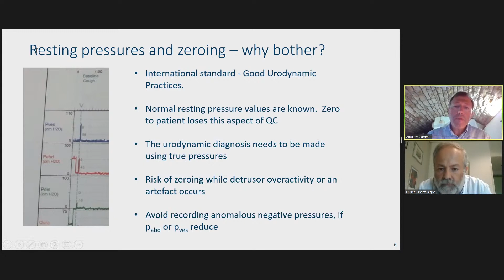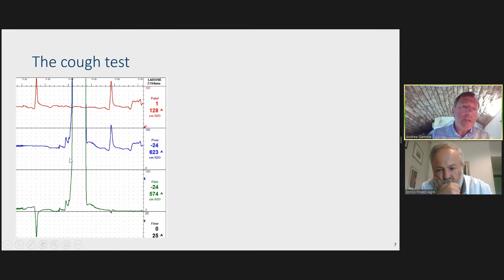So if I move us on to the next item of quality, which is the cough test, and many of us are familiar with this, I'm sure. Here's a good example where the patient coughs on this left-hand side, and the abdominal pressure goes up beautifully, but there's absolutely flat on the vesical line. And this huge pressure rise here is the flush through, where we're pushing water through the dome, and look what happens afterwards. It's restored. Vesical and the abdominal line go up together beautifully and nicely subtracted out with very little movement on the detrusor. So probably what the issue was here was an air bubble in your water-filled system, and it just needed pushing out, so you got a water column only transmitting your pressure.